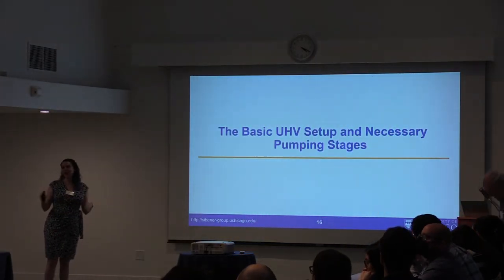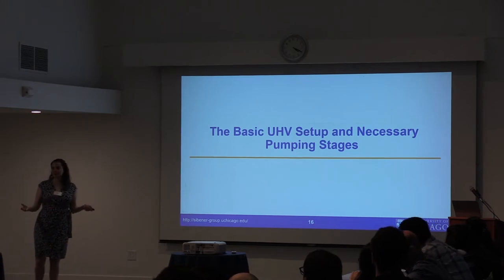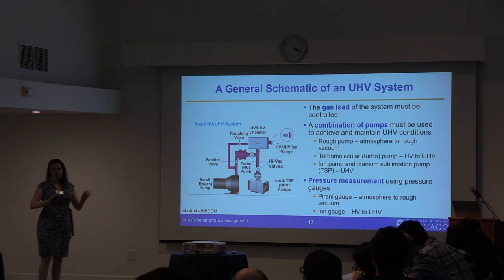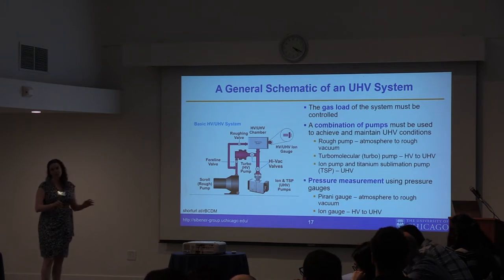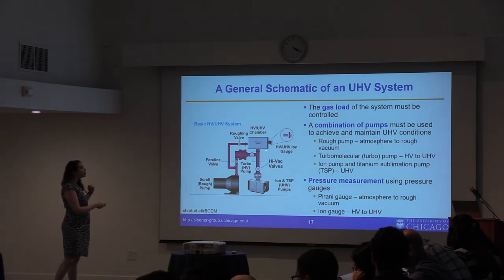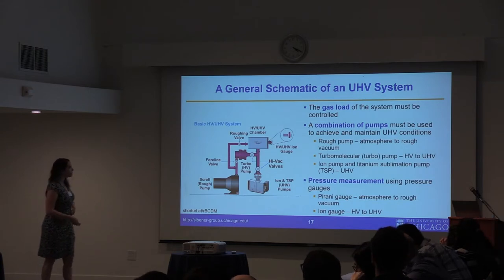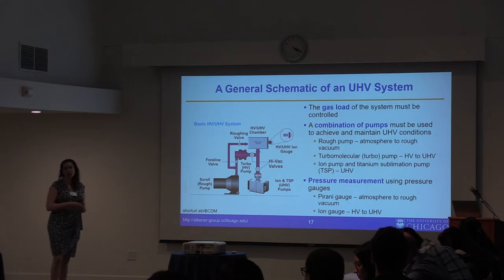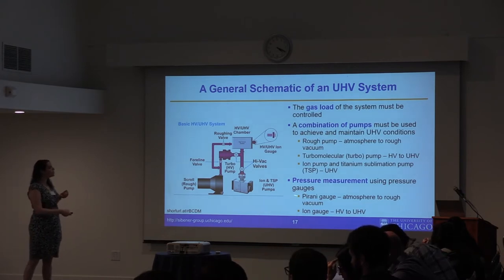We've given some context of why UHV and different parameters to consider, but how do you actually get it? You need a variety of different pumping stages to move from atmospheric pressure to UHV conditions. When looking at a UHV system, you have a scroll or rough pump going from atmosphere to rough vacuum, then a turbo pump taking you from high vacuum toward UHV conditions, and then an ion pump or titanium sublimation pump to get even further into the UHV regime. You need all these components connected so gas can flow efficiently and you can maintain UHV pressures detected by your gauges.